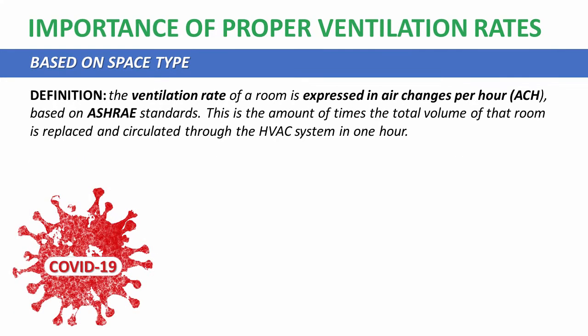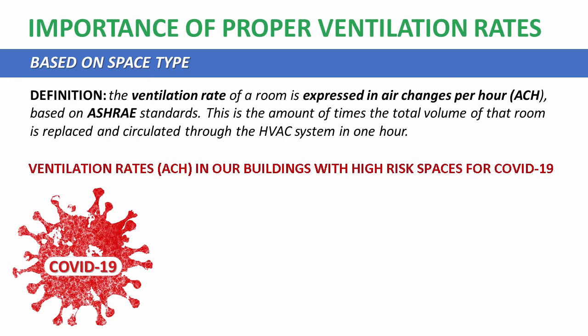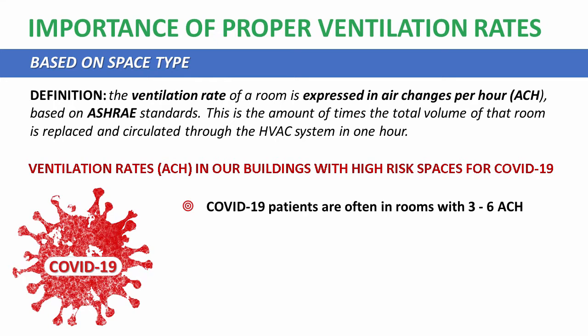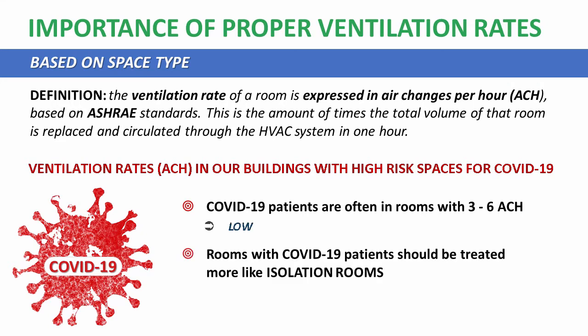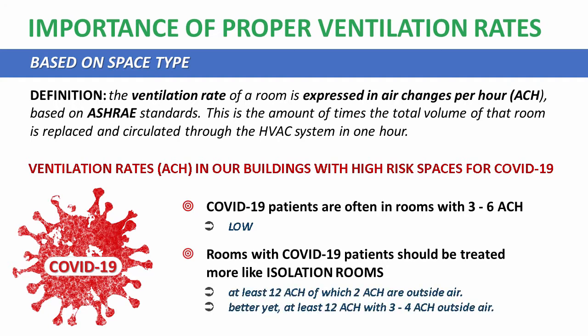Let's look at what is going on now with the COVID-19 situation. In our buildings, whether hospitals or nursing and elderly homes, we see that COVID-19 patients are often in rooms with only 3 to 6 air changes, and that is low. Rooms with COVID patients should be treated like isolation rooms and should have at least 12 air changes, of which 2 should be outside air. Better yet, at least 12 air changes with 3 to 4 outside air.